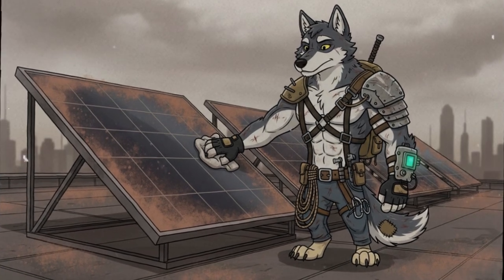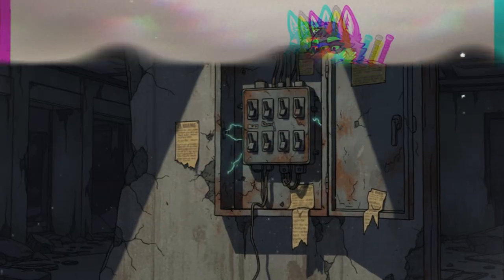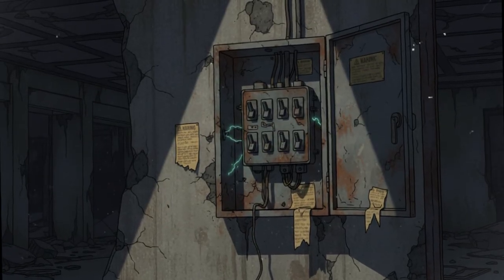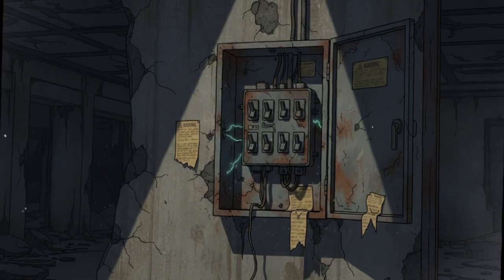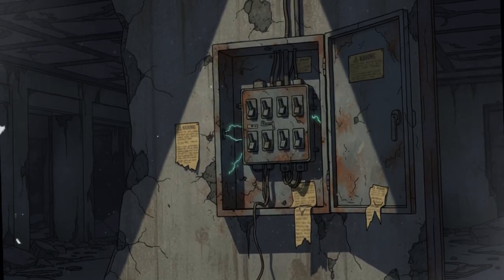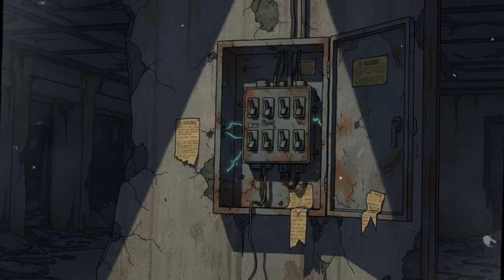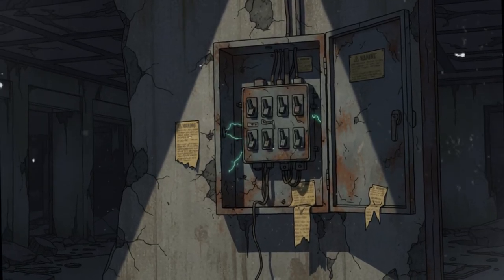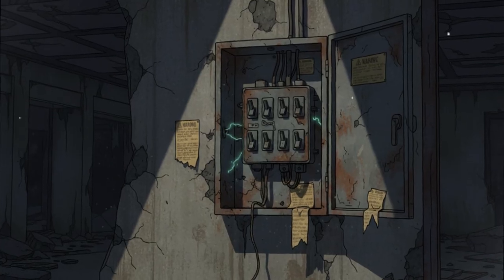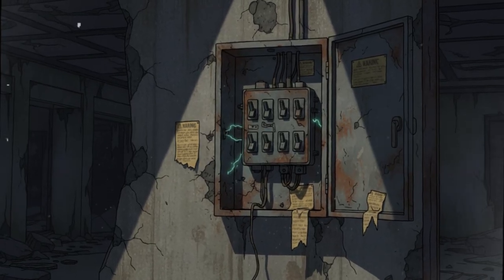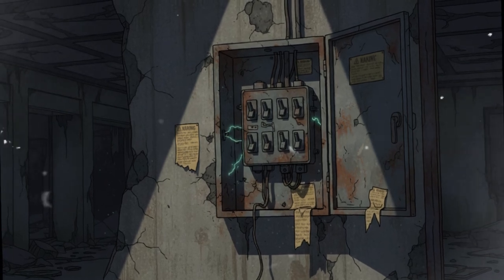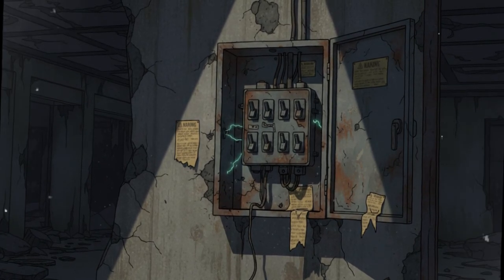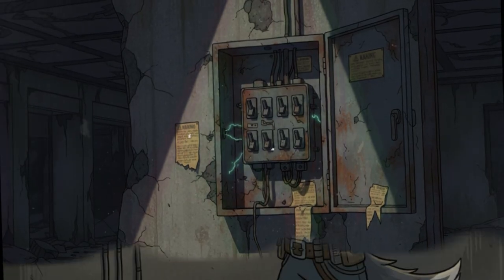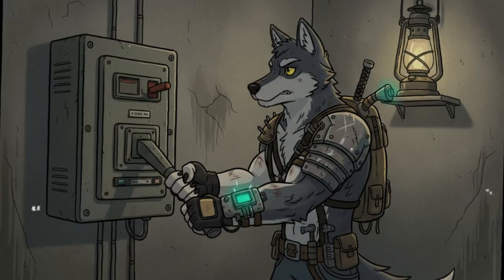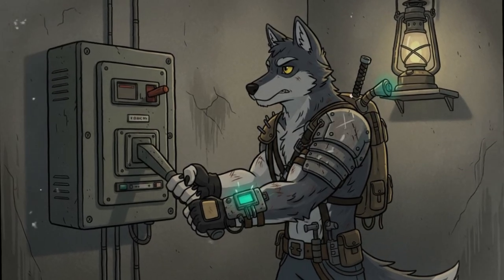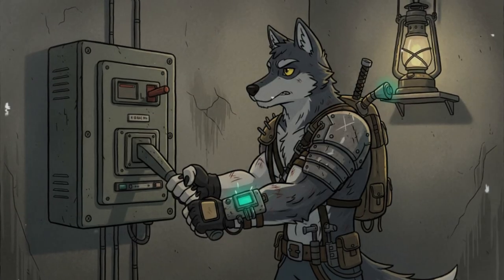The survival implication escalates when we consider transformer vulnerability. High-voltage transformers are massive, custom-built machines that can weigh hundreds of tons. Manufacturing lead times can stretch many months. They are protected by physical security measures and monitoring, yet they remain single points of failure in certain corridors. A severe geomagnetic storm induced by solar activity can generate currents in long transmission lines, saturating transformer cores and causing overheating. This phenomenon is documented in space weather research and past events, including regional blackouts triggered by geomagnetic disturbance. Utilities mitigate this risk with monitoring systems and operational procedures to temporarily reduce load during solar storm alerts. But the physics cannot be negotiated, it must be managed.